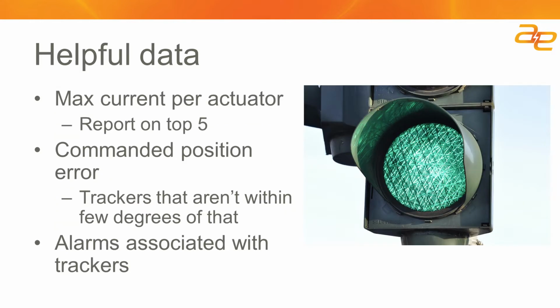Max current per actuator: tell me the 5 actuators with the highest current draw over the course of a day, and run that report every day for 2 or 3 weeks. If the same actuators keep showing up, you've got a potential O&M issue upcoming, and you have time to plan what to do about it, rather than waiting till there's a failure.